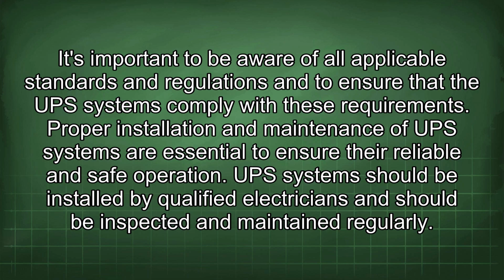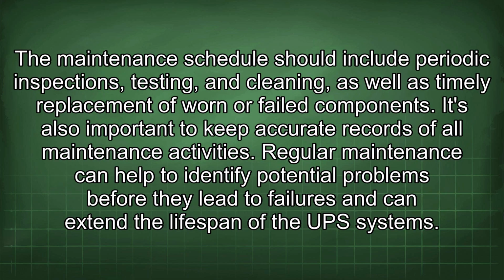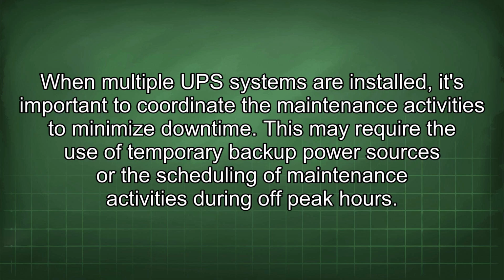UPS systems should be installed by qualified electricians and should be inspected and maintained regularly. The maintenance schedule should include periodic inspections, testing, and cleaning, as well as timely replacement of worn or failed components. It's also important to keep accurate records of all maintenance activities. Regular maintenance can help to identify potential problems before they lead to failures and can extend the lifespan of the UPS systems. When multiple UPS systems are installed, it's important to coordinate the maintenance activities to minimize downtime. This may require the use of temporary backup power sources or the scheduling of maintenance activities during off-peak hours.